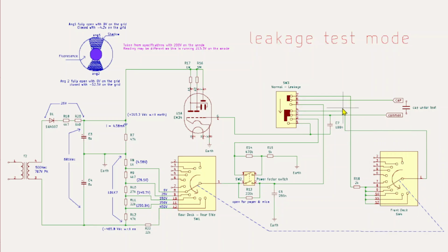Well, you'll notice that this part of the switch here, one side of it connects to the common when it's in normal mode, so it connects up here to the common. The other side goes up, and in normal mode it connects to the capacitor. So as soon as you let go of that switch and it returns by spring back up, straight away when you're in the leakage positions, it switches that 2k resistor across the capacitor, and so that's how they discharge the capacitor and make it safe.